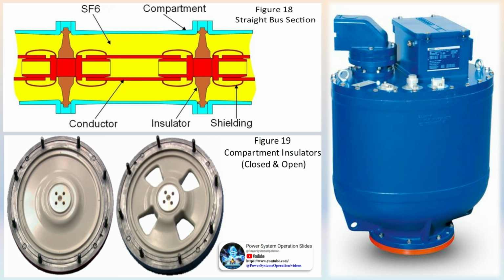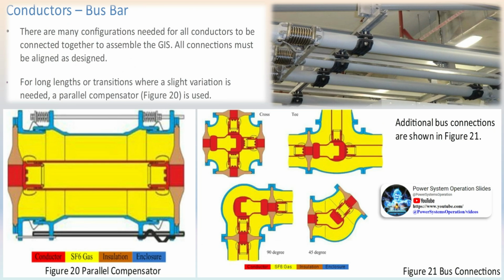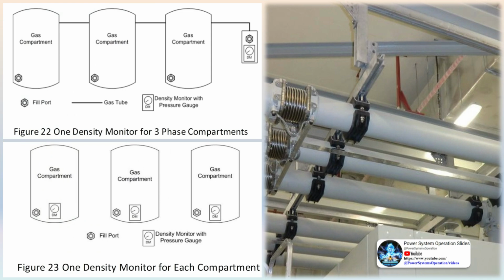Joining and sealing enclosure modules. GIS enclosure modules are joined together using bolted flanges which have an O-ring sealing system for the enclosure. The conductors have a sliding plug-in contact for connecting the conductor sections. Rupture discs. Rupture discs are commonly used as a safety measure in pressure vessels, although the pressure rise caused by internal fault arcs within a GIS compartment of the usual size is predictable and gradual enough that the protective system will interrupt the fault before a dangerous pressure is reached.